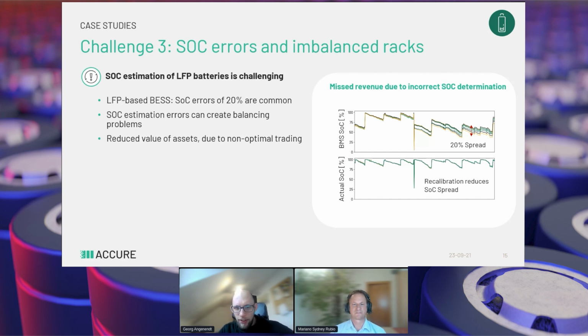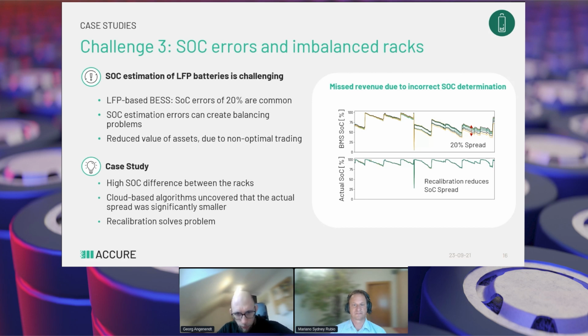On the right-hand side you again see a real-life example. We found a high SOC difference between different racks, and we were able to show that the actual spread was significantly lower - it was really a BMS SOC estimation issue. We worked on a recalibration, which solved the problem.